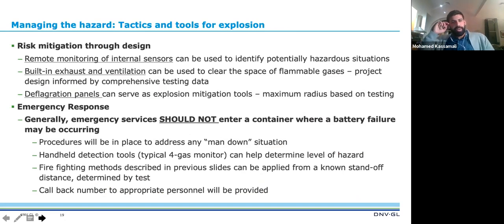As previously mentioned, we can manage this explosion hazard with built-in exhaust and ventilation, similar to what I discussed for the fire hazard. We can remove these flammable or explosive gases prior to their buildup becoming a concern, triggered by a gas detection system that tells the HVAC system to get the gaseous volume out and bring in new air.